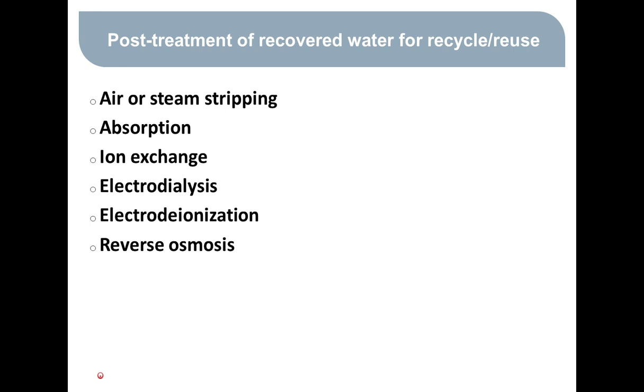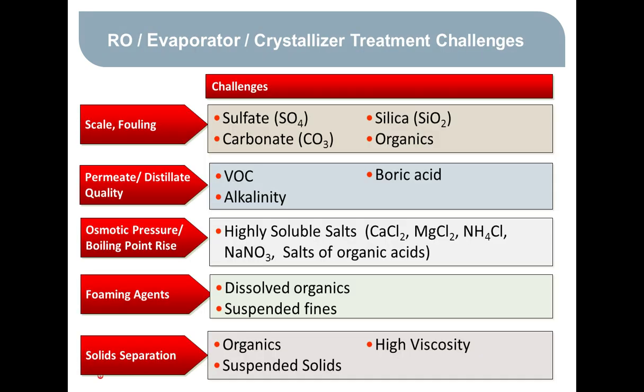And if the downstream process where the water is going to be reused can stand that, it's fine, but otherwise you're going to have to do some things to remove any impurities, depending again on what purpose you're going to reuse the water for. So these are some of the things that might be involved in post-treating the recovered water. So now that we know what unit operations are involved, let's talk about some of the things that we have to consider in designing these processes. In particular, we're going to be concerned with things like scaling and fouling in any kind of thermal system, or an RO system for that matter as well.